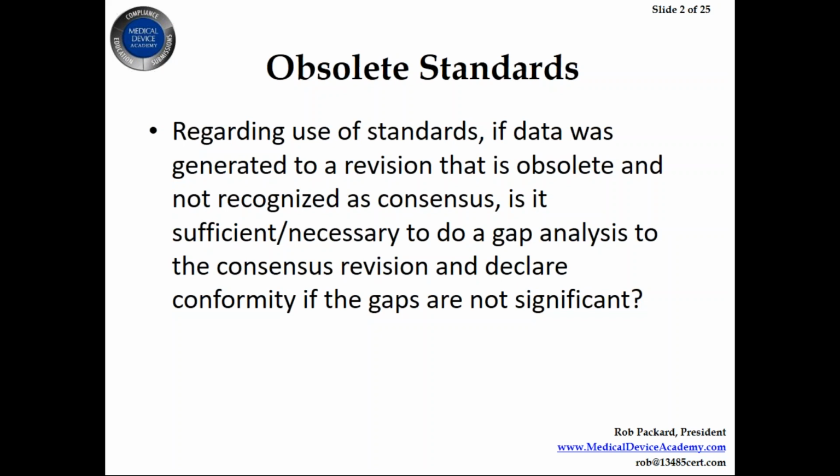Yes, you should do a gap analysis, but if there are differences, you have to show data to address the differences. You can't just say, they're not that significant, so don't worry about it. There was a reason why they changed the standards, and they want you to do the testing according to that new one. So if they've made a change, you're going to have to do at least some testing to cover the bridge between the old version and the new version.